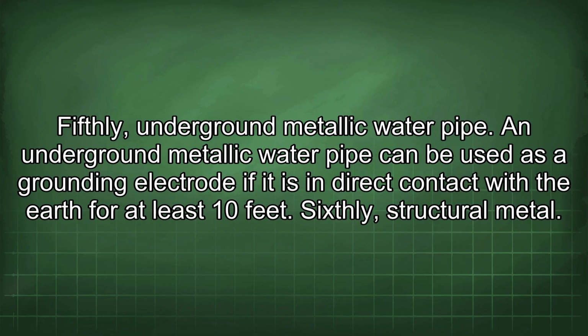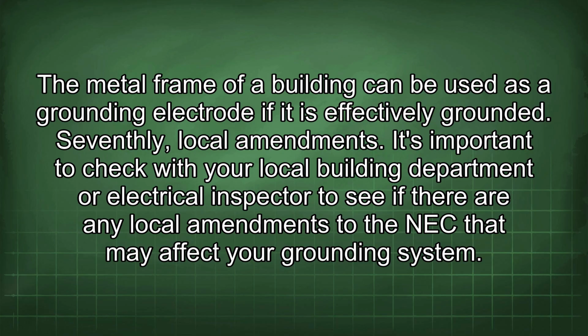Fifthly, underground metallic water pipe. An underground metallic water pipe can be used as a grounding electrode if it is in direct contact with the earth for at least 10 feet. Sixthly, structural metal. The metal frame of a building can be used as a grounding electrode if it is effectively grounded. Seventhly, local amendment. It's important to check with your local building department or electrical inspector to see if there are any local amendments to the NEC that may affect your grounding system.